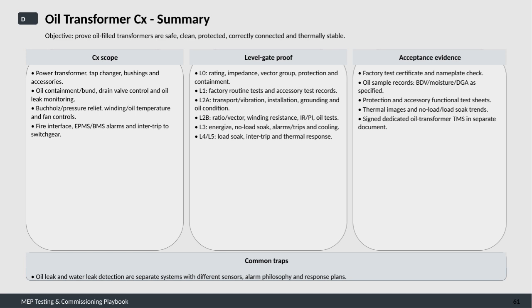We also verify the oil containment system, including the bund and drain valve controls, as well as oil leak monitoring. Essential protection devices such as the Buchholz relay, pressure relief valves, and temperature controls for windings, oil, and fans are thoroughly tested. Additionally, the integration with fire detection systems, EPMS and BMS alarms, and inter-trip functions to the switchgear are confirmed to work perfectly. The commissioning is organized into level gates, which help structure the process and ensure comprehensive testing.